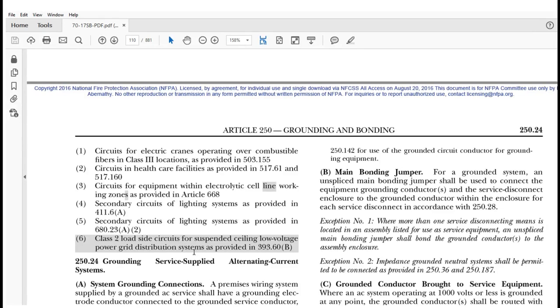All right. So in this case, it doesn't need to be grounded, and all the code did here was add an item 6 to 250.22 for circuits not to be grounded, with the addition of now Class 2 load side circuits for suspended ceiling low voltage power grid distribution systems. And it expresses that in more detail in 393.60(B). So that was the change that took place for the 2017 when it came to just adding another circuit that is not to be grounded. All right, so that was your significant change in that one.